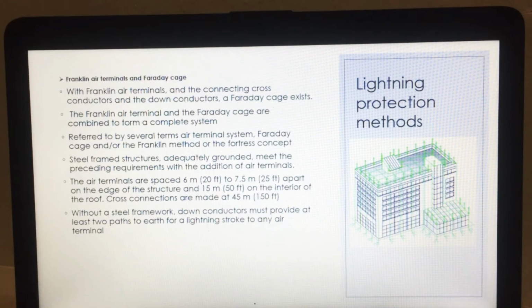You can see on this one and this one, it's produced a Faraday cage. The Franklin air terminal and the Faraday cage are combined to form a complete system, referred to by several terms: air terminal system, Faraday cage, the Franklin method, or the fortress concept. A steel frame structure adequately grounded meets the preceding requirement with the addition of air terminals.